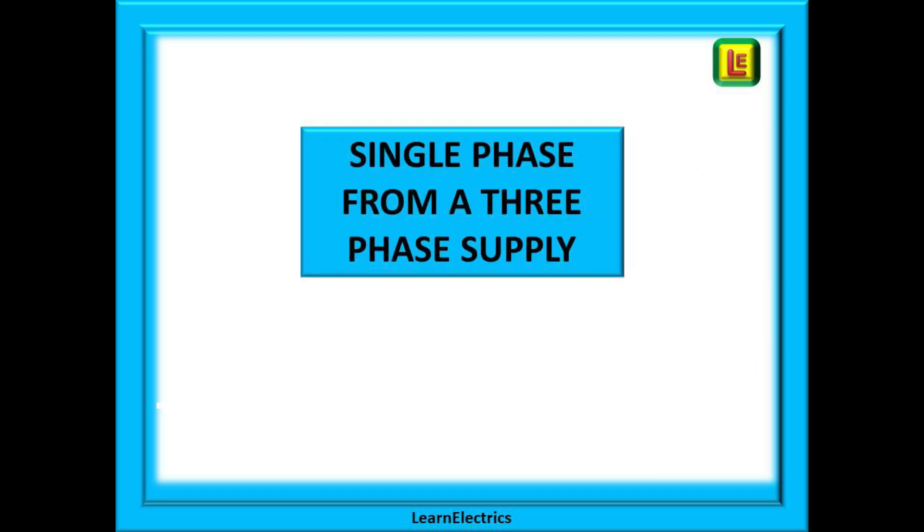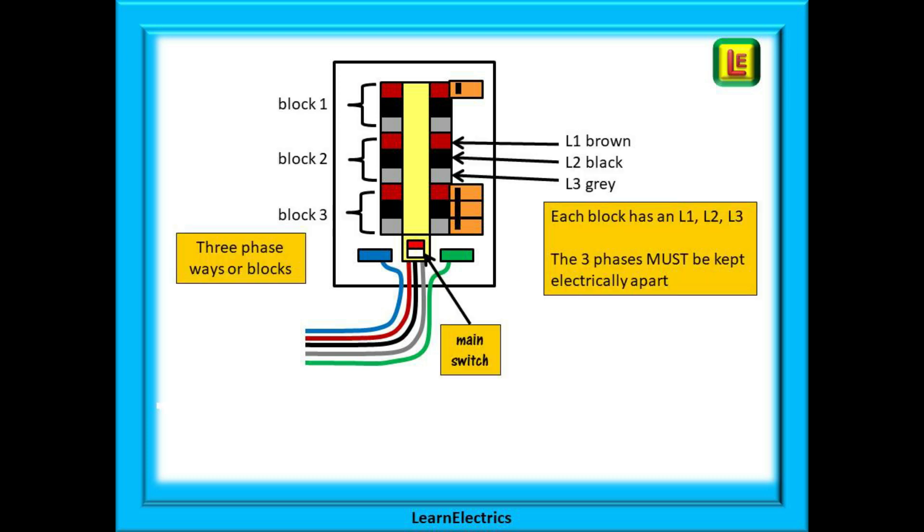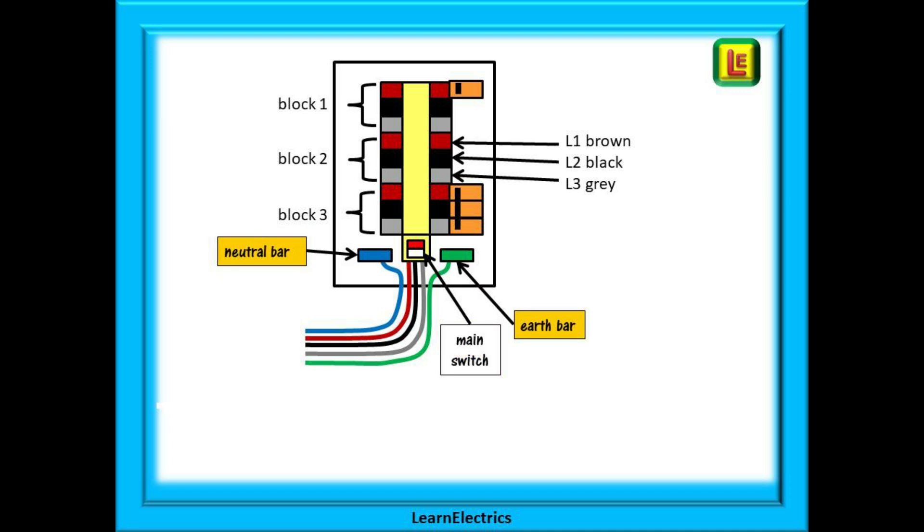Another question that we are often asked, how do we get a single phase supply from a three-phase distribution board? Let's look at this. Here we have a very basic sketch of a three-phase distribution board. On this board, there are six three-phase ways, three on the left and three on the right. Each way is a block of three phases, shown here as brown, black and grey, L1, L2, L3. These phases, L1, L2 and L3, must always be kept electrically separated from each other. And we have shown the main switch that will turn off all the power to the board. There is also a neutral bar and an earth bar. The supply cable brings five conductors into the distribution board. The three phases, plus neutral, plus earth.